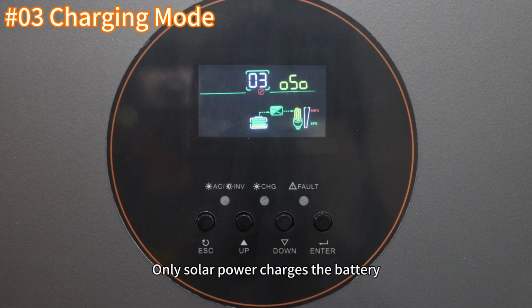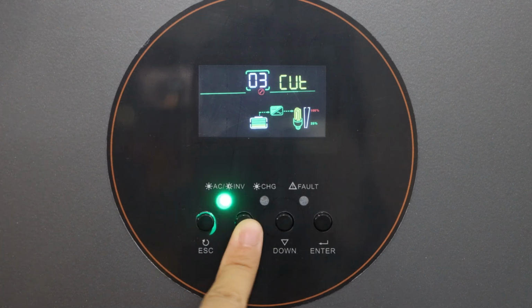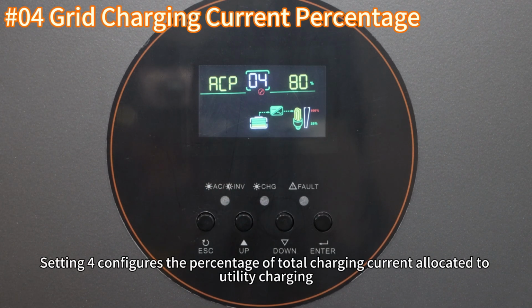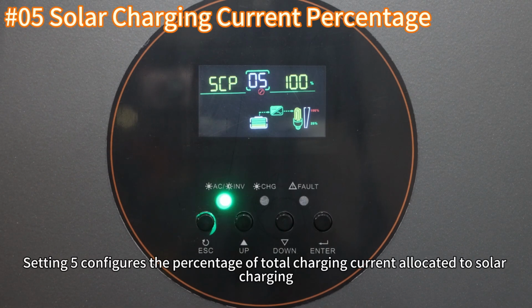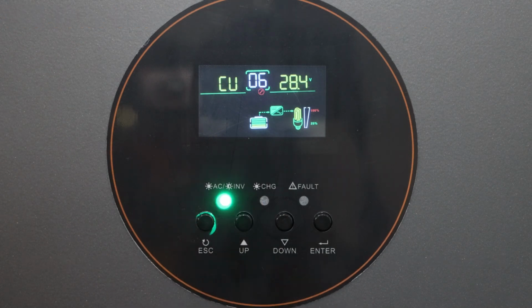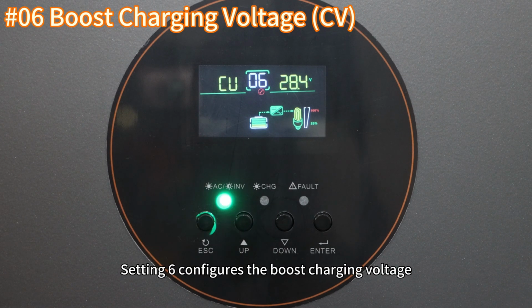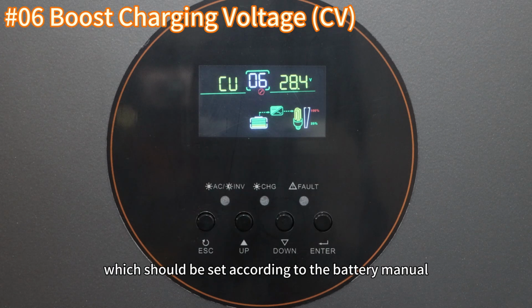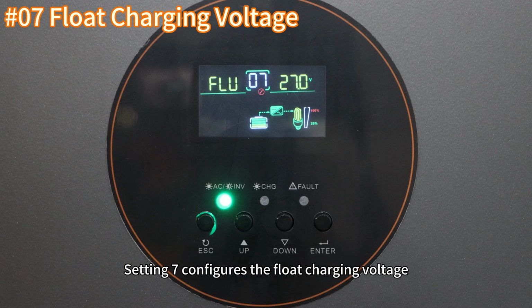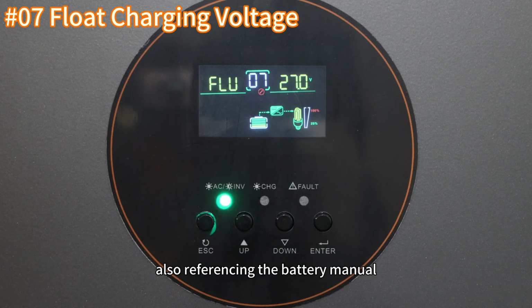OSO mode, only solar power charges the battery. Setting 4 configures the percentage of total charging current allocated to utility charging. Setting 5 configures the percentage of total charging current allocated to solar charging. Setting 6 configures the boost charging voltage, which should be set according to the battery manual. Setting 7 configures the float charging voltage, also referencing the battery manual.